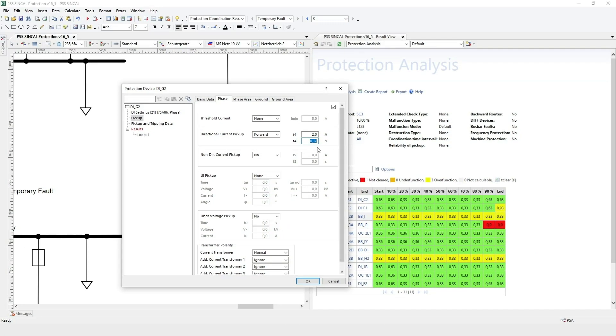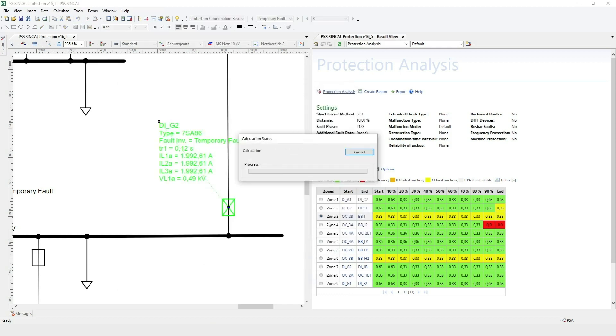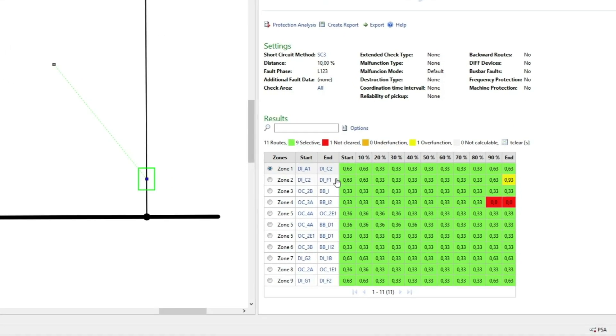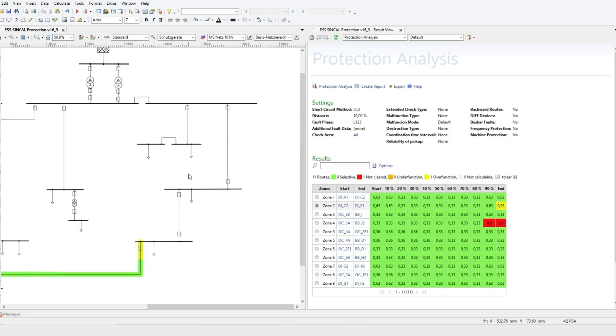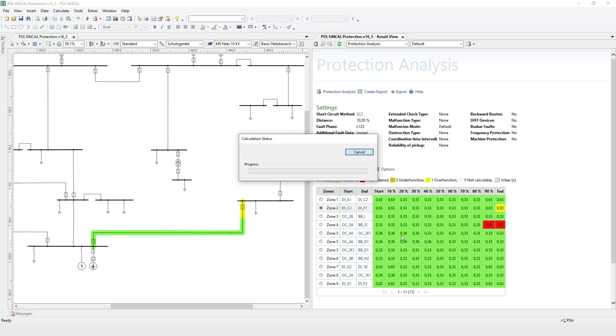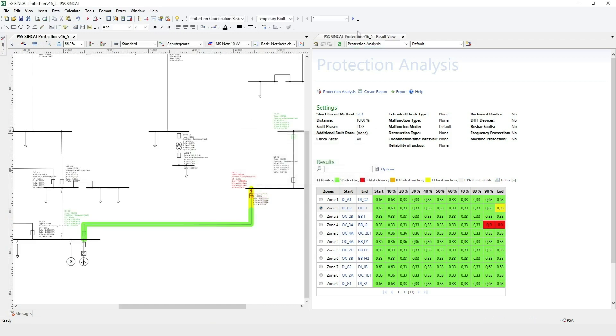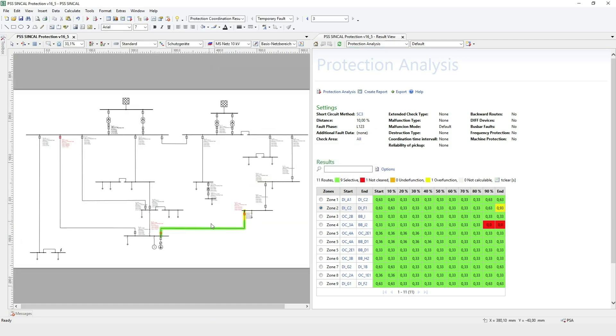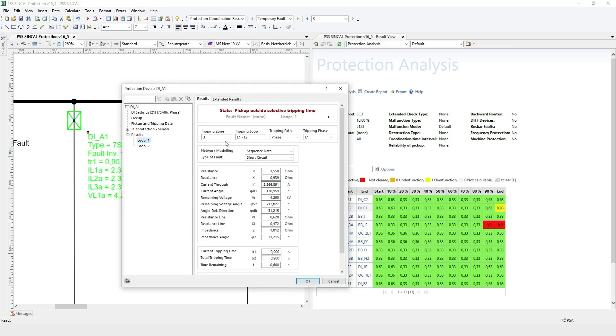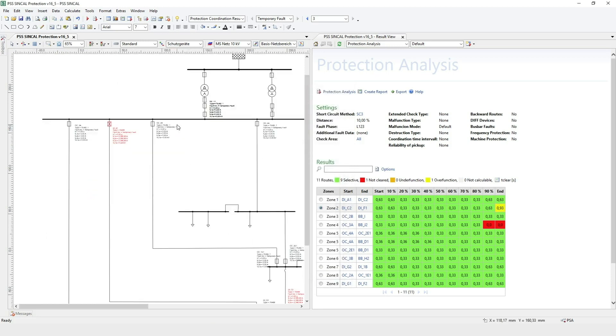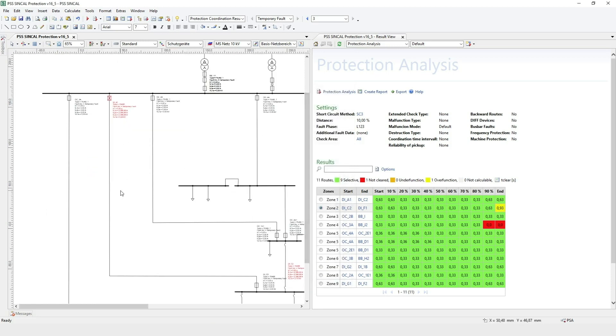Let's make that change and perform the protection analysis again. Now you can see that many of the over-functions disappeared. Looking at the leftover over-function, we perform the protection simulation and see we again have an unwanted operation — the third zone tripped. For distance protection devices, usually the first and second zone cover the main protection area, and in this case it's this line, so the tripping here seems to be correct.